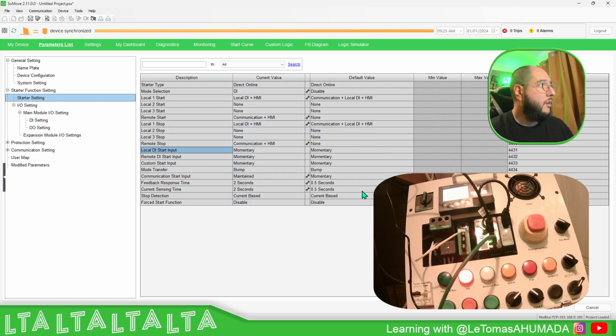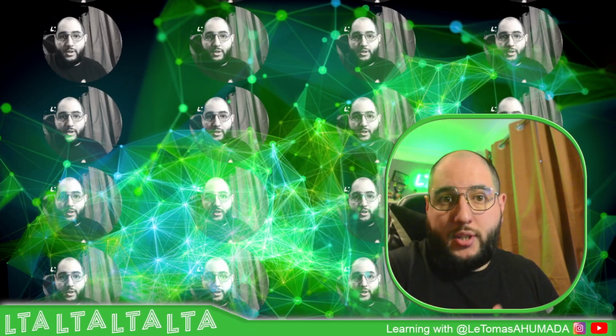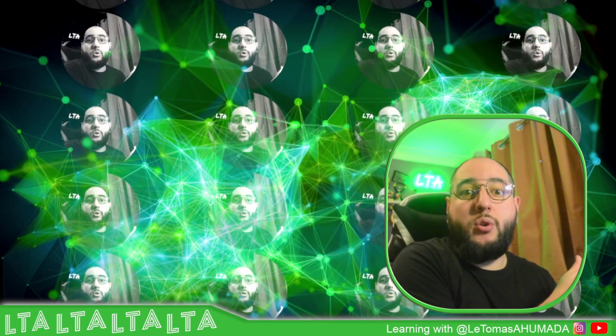So we have the possibility to define if you're using momentary or maintain. That may be related to the 2 and 3 wire control that we had in the past with TeSys, but this is a different naming. With momentary, you need 2 signals, and if it's maintain, you need just 1 signal, and that can be applied to the digital input or to the communication control word.